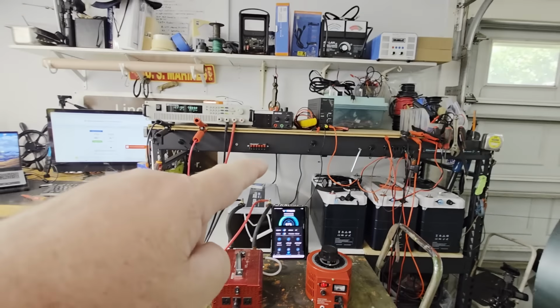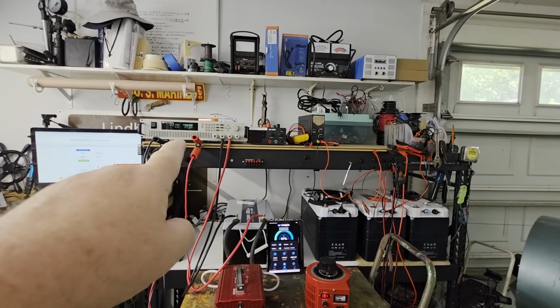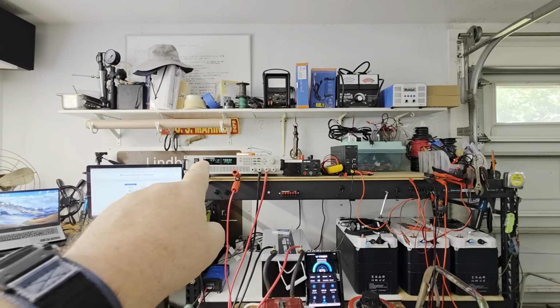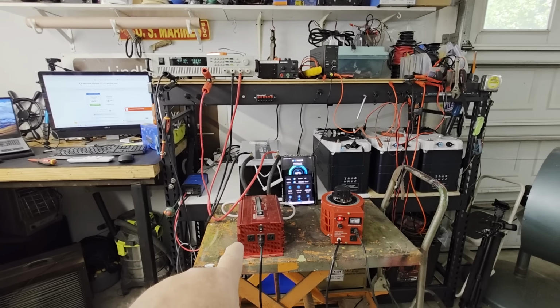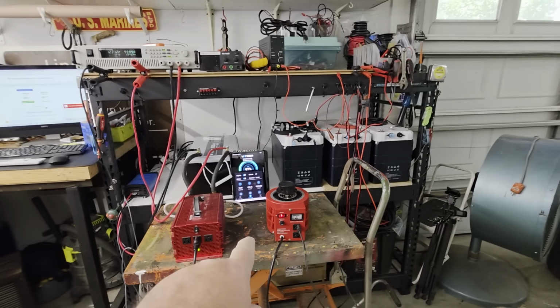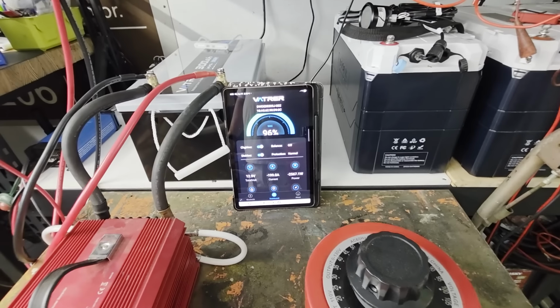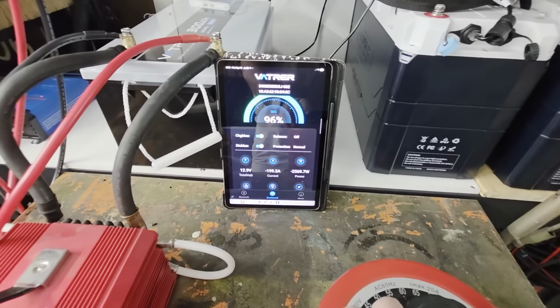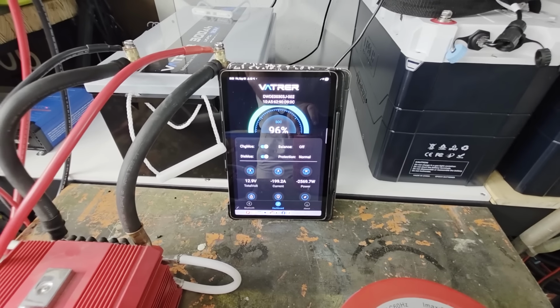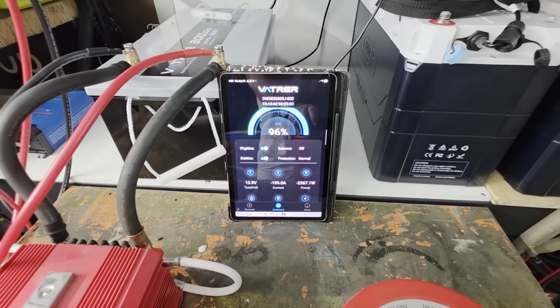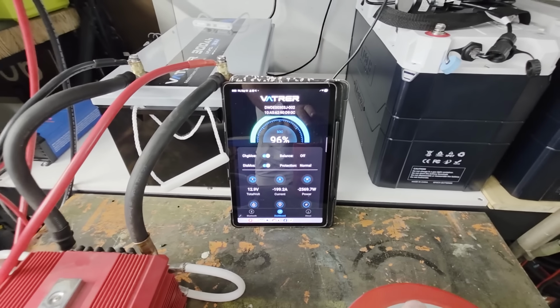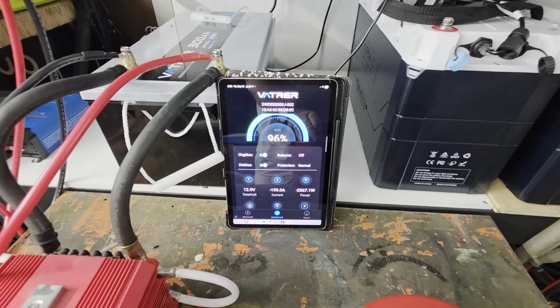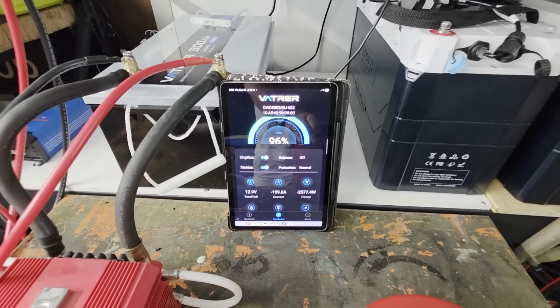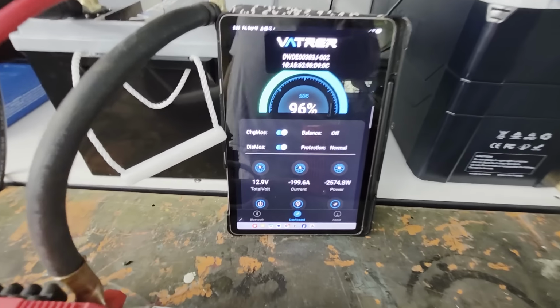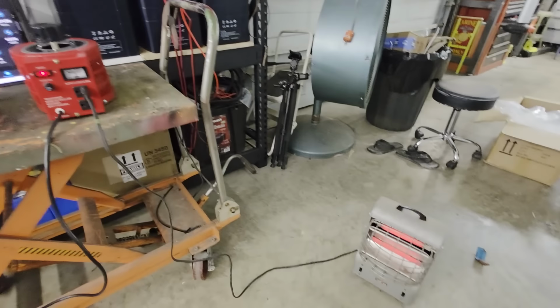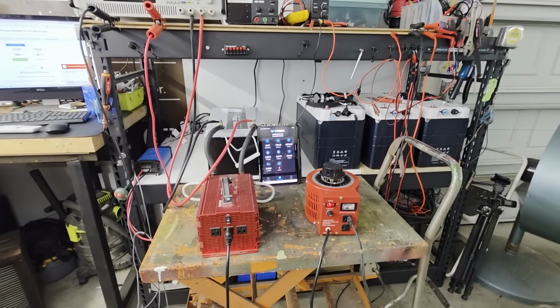So again, here's the rig. We've got the electronic load, setting up a load for 80 amps. Right now we're at 79.99. In addition, we have the 2000 watt inverter going through the variac so we can adjust it, and it looks like it's working pretty good. I'll have to adjust it up just a hair. Let me see if I can adjust it up a hair. I'll probably overshoot. The control on this variac is pretty good. That's pretty good, we're just going to leave it alone. Alright, let's let it run, we'll come back to it.